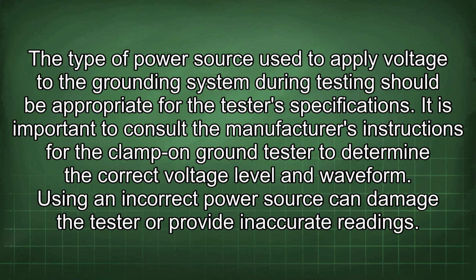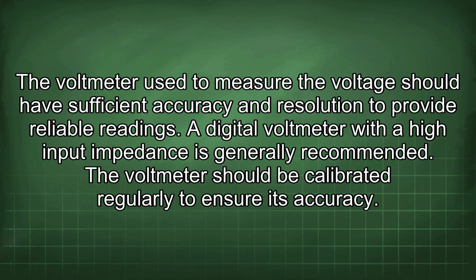The type of power source used to apply voltage to the grounding system during testing should be appropriate for the tester's specifications. It is important to consult the manufacturer's instructions for the clamp-on ground tester to determine the correct voltage level and waveform. Using an incorrect power source can damage the tester or provide inaccurate readings. The voltmeter used to measure the voltage should have sufficient accuracy and resolution to provide reliable readings. A digital voltmeter with a high input impedance is generally recommended. The voltmeter should be calibrated regularly to ensure its accuracy.